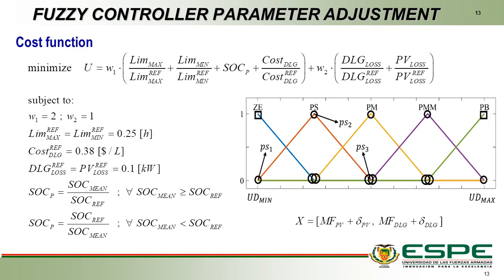This is the cost function that considers the reference value of the battery state of charge limits, the reference values of the total price of fuel consumption, the reference values of the power losses by the generation source, and the objective function that tries to keep the battery state of charge oscillating close to 60% of the battery charge.